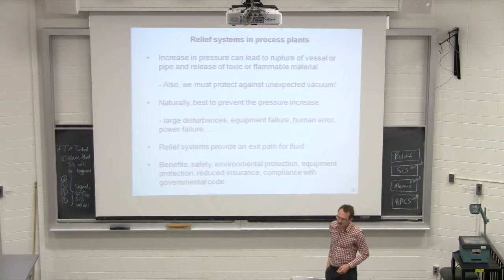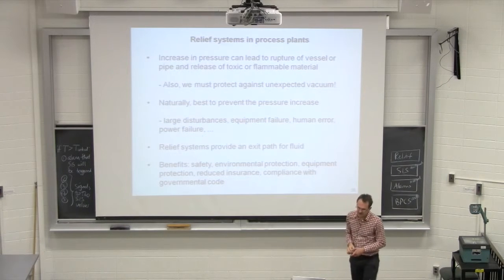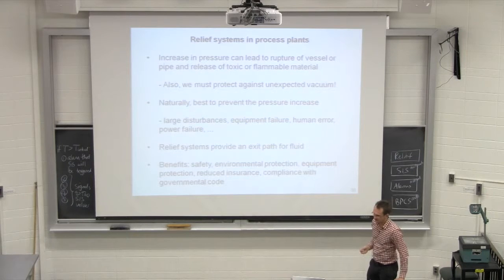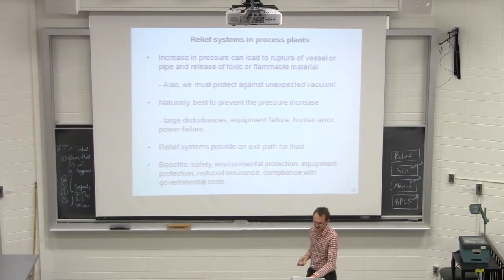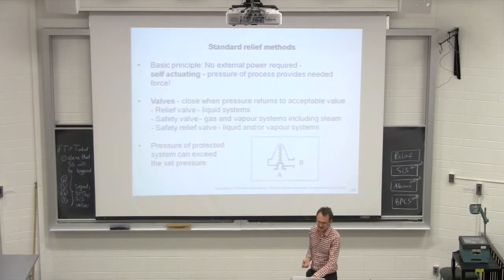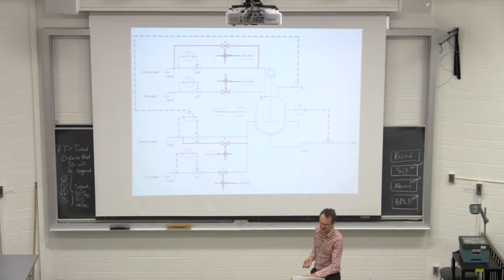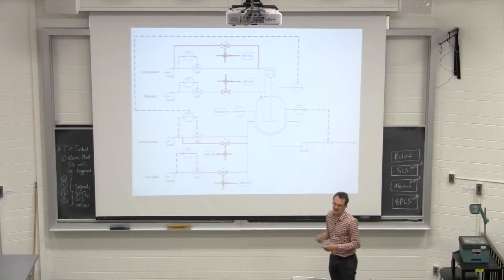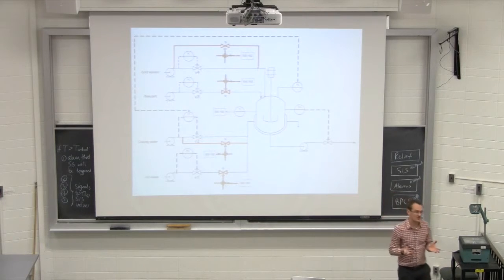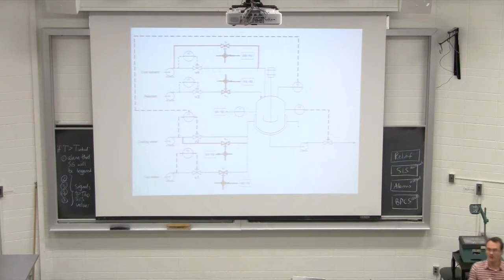Okay? So the principle of the relief is the following. Vessels that we use have a safety rating. So let me go back perhaps to this diagram we looked at, the CSTR. That's a closed vessel that's purchased. On the side of the vessel, you will always see the operating pressure, as well as the maximum operating pressure.